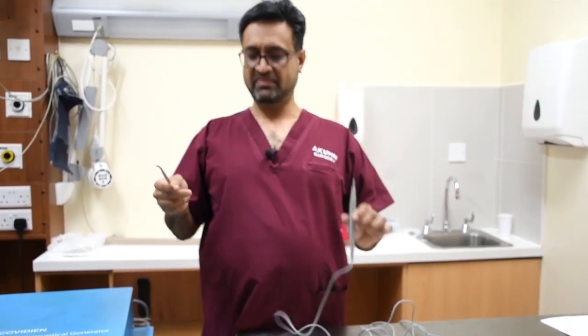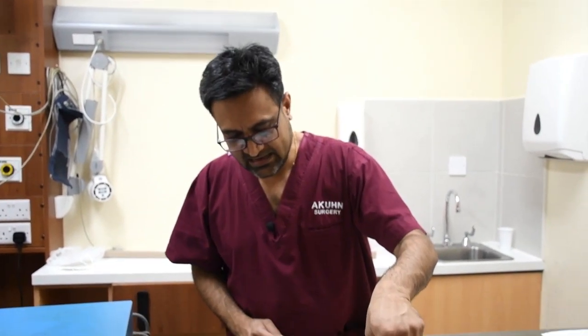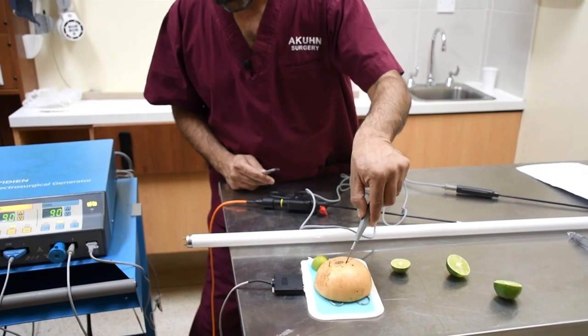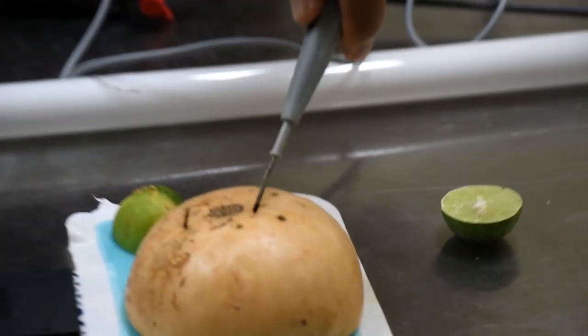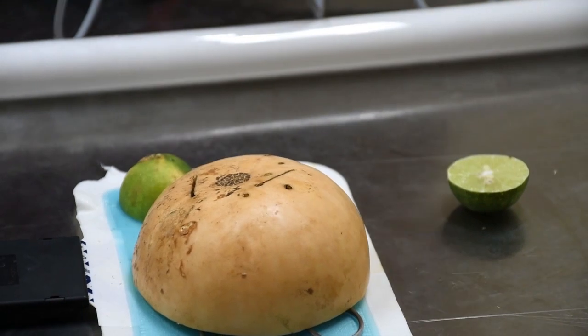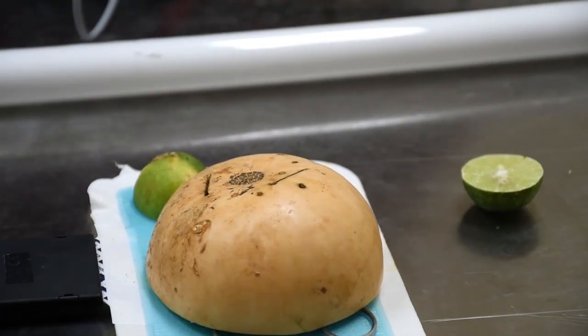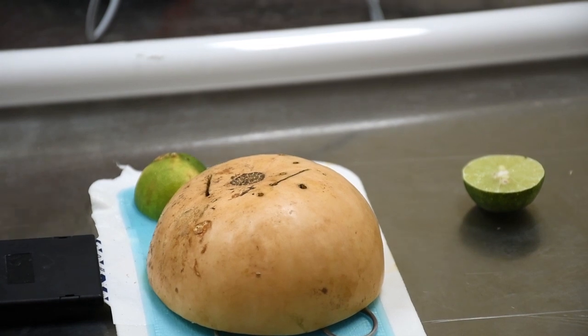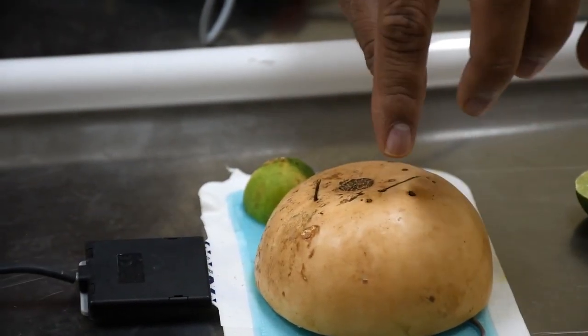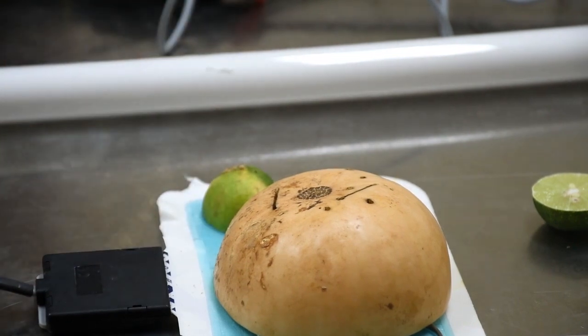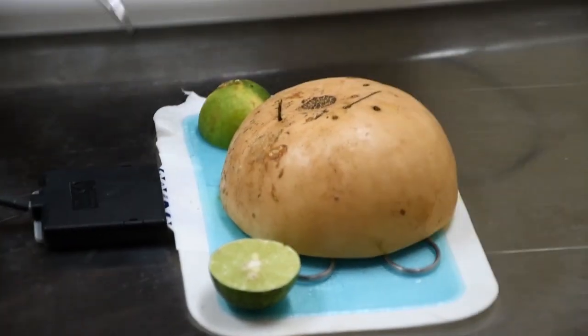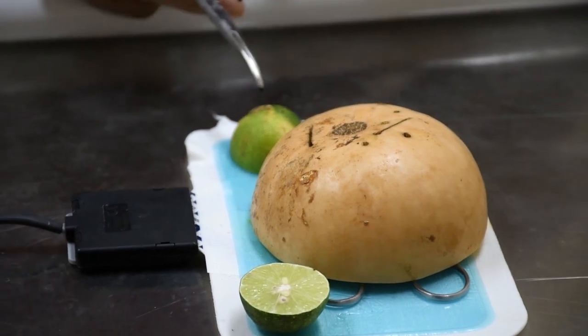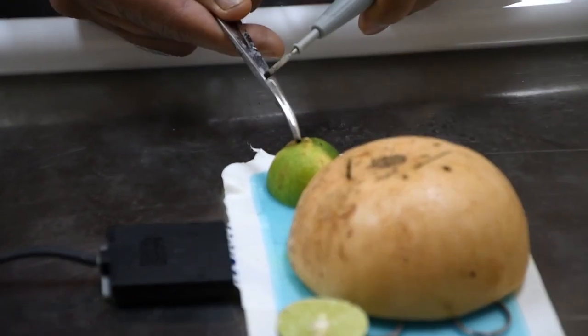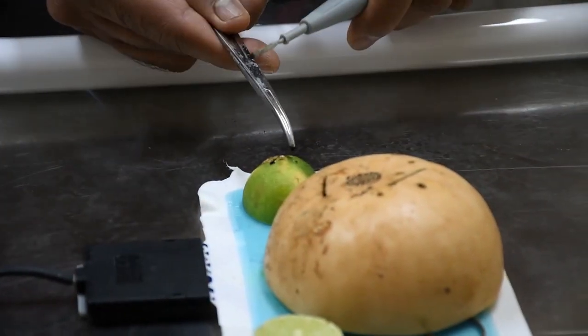So we have to understand one thing. Why is this not burning? This is density. So you're having a thin tip and you're getting the effect of a cut, but you have a broad surface taking the electricity out. You cannot convert it. But what's happening is that the same amount of electricity going in here to cause this is coming out through here and returning. Now we have to understand one thing to see the difference that will be seen in this. Now look at this return. I am going to cause a burning here. Can you see? It's very high.